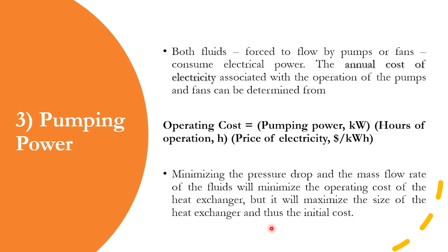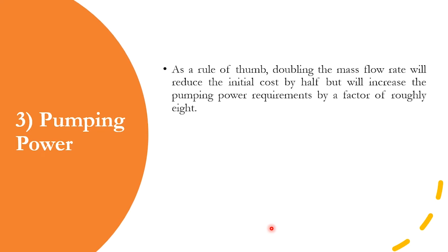Minimizing pressure drop and mass flow rate reduces operational cost, but increases the size of the heat exchanger, which increases initial cost. There is a rule of thumb: doubling the mass flow rate reduces the initial cost — linked to exchanger size — by one half, but leads to an increase in power requirements by a factor of eight. So you always have to find a trade-off, just like in distillation between number of trays and reflux ratio.